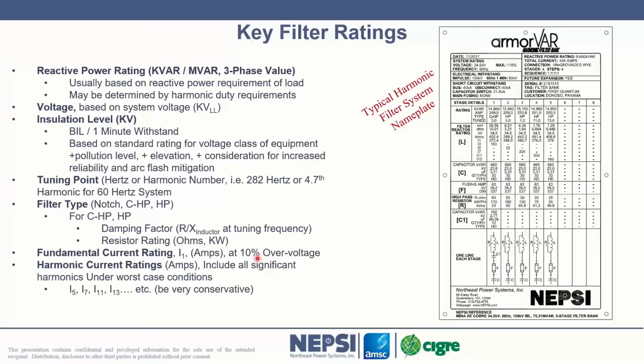And then finally, harmonic current ratings. What are the harmonic current ratings? What harmonic currents do we expect to flow into each of these branches? And I make a statement here to be very conservative. I can't overstress the importance of being conservative. When you develop a harmonic filter, if you are not conservative, it will come back and bite you.